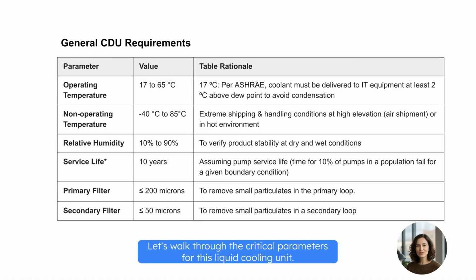Let's walk through the critical parameters for this liquid cooling unit. First, look at the operating temperature, 17 to 65 degrees Celsius. The key number here is the floor, 17 degrees. Why 17? This is directly tied to ASHRAE guidelines. We must maintain the coolant temperature at least 2 degrees above the dew point to prevent condensation. If we go lower than 17, we risk water forming on the IT equipment, which is a failure condition.